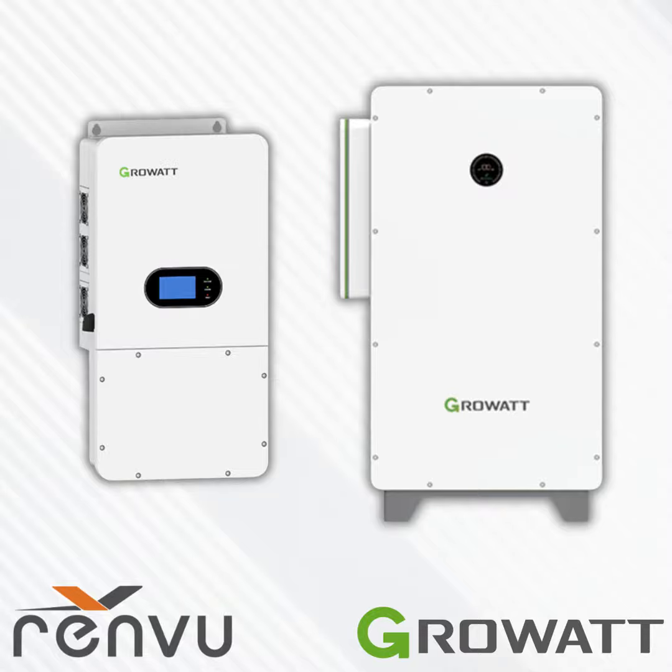With regards to communications, just a quick overview, we offer LAN, Wi-Fi, and 4G with a plug-in dongle. We have Modbus RTU communication over RS-485, standard on every WIT. We're also happy to share the Modbus register map with an NDA. We have generator start and stop function built into the inverter. So for completely off-grid with a backup generator kind of applications, we can support that and manage it so that our inverter is the primary.